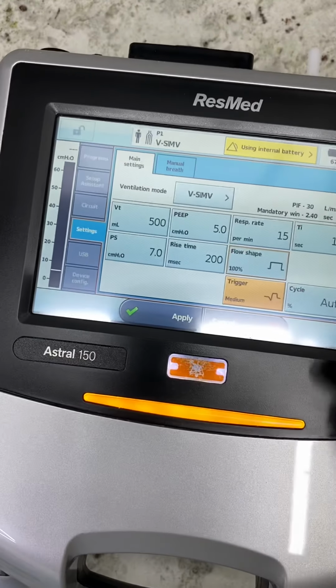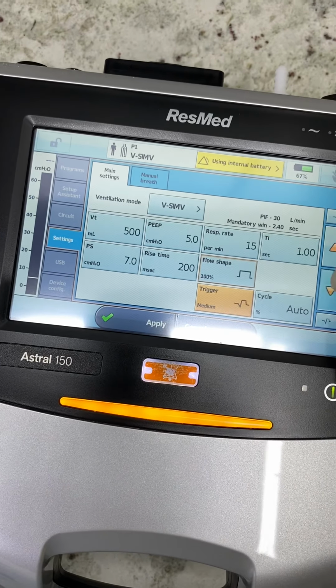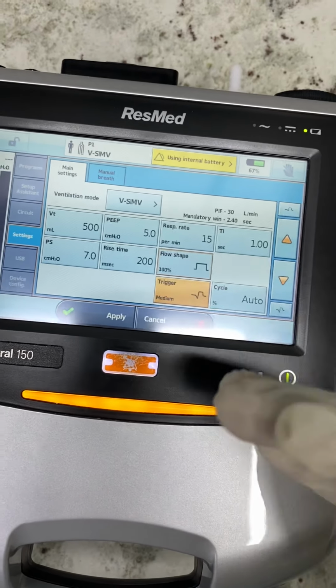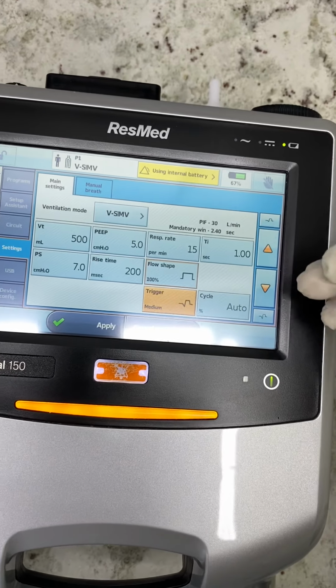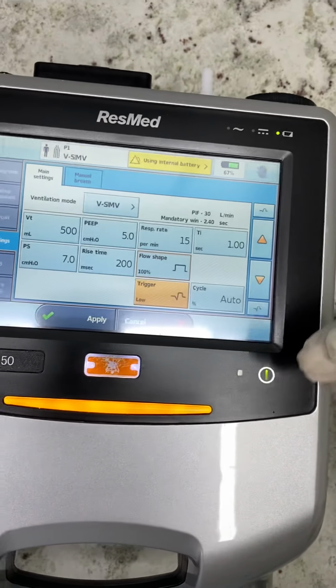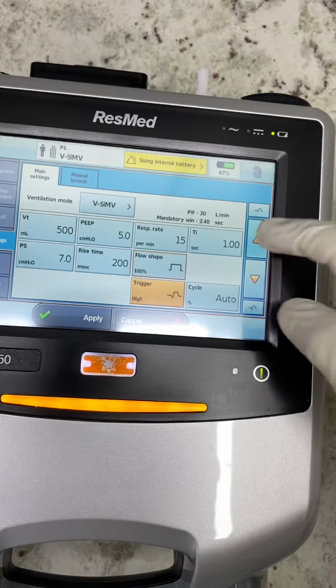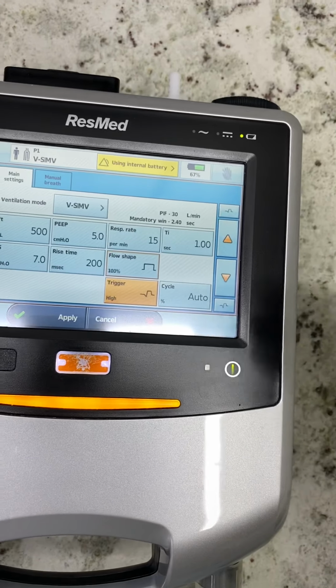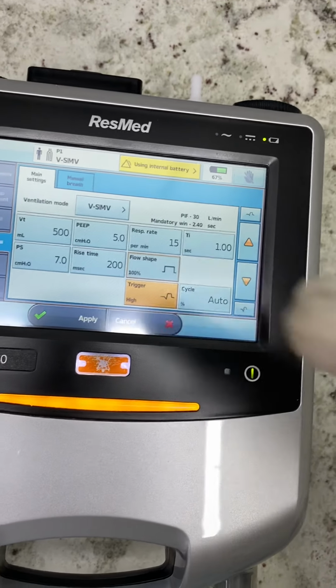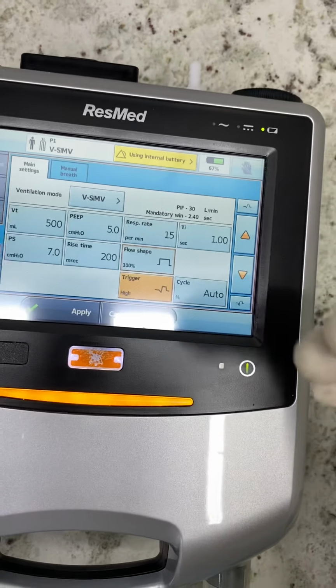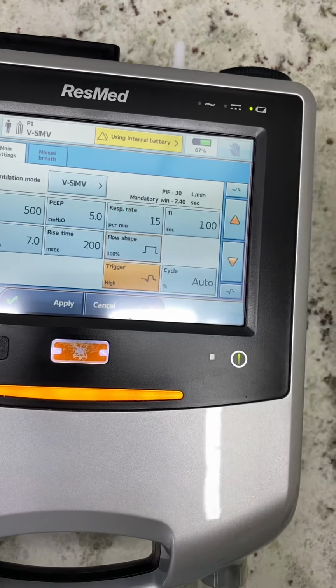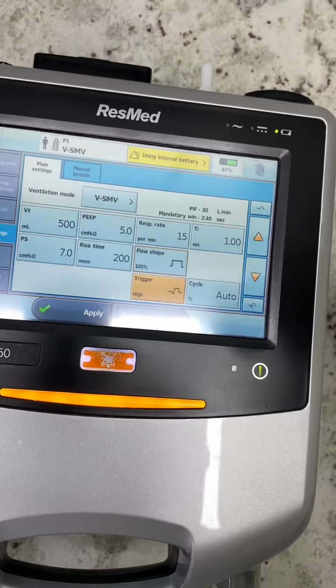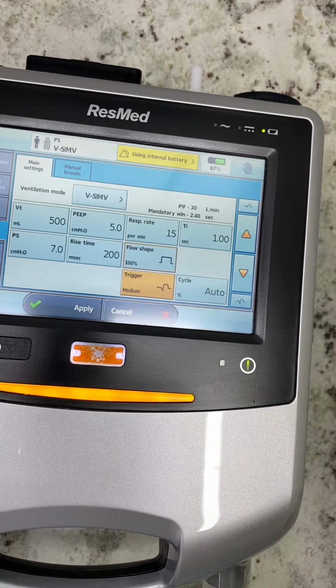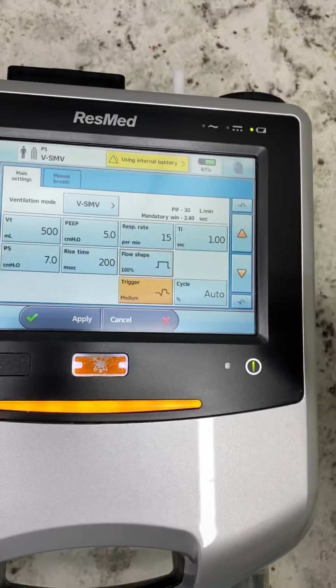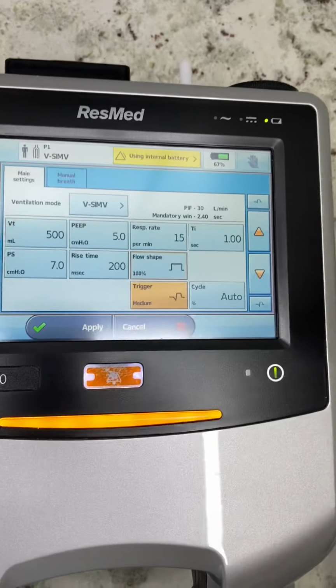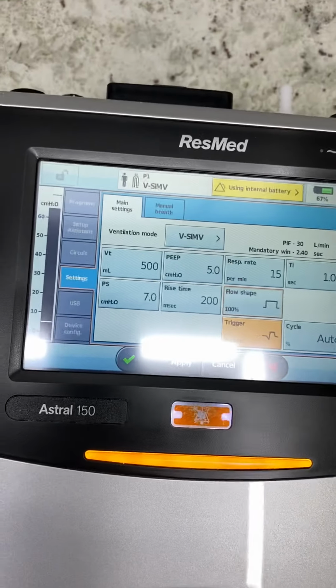And trigger. The trigger, I'll tell you, we have 3 settings: high, medium, and low. So how the trigger works here is that low means low sensitive, medium means medium sensitive, and high means high sensitive. So it's not the other way around. It's just like what it is saying. High trigger means it's high sensitive trigger. So the patient's every effort will be sensed. And medium means medium. So we usually keep on medium, but it depends on you. If you want it more sensitive, you can keep it higher. And cycle, you can keep it auto, not a problem.